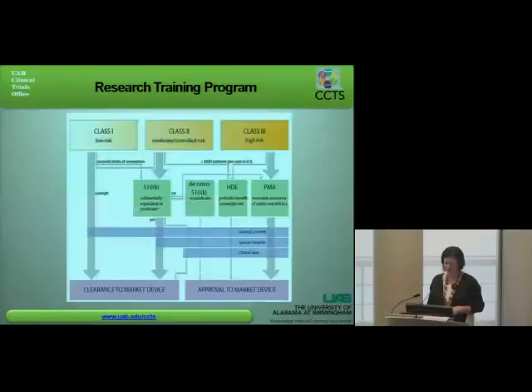And it breaks down Class 1, Class 2, and Class 3 devices and the process that you would have to go through in order to market that device. It asks some very simple questions, gives good information. They also have a PowerPoint presentation that you can look at online that's very good as well. This is another simple flow chart that you can look at to help decide what route you would have to take to market your device.